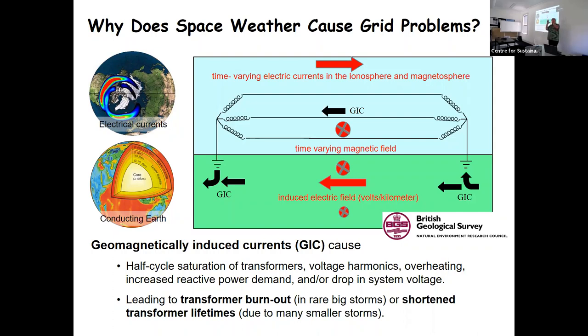It was the harmonics that ended up taking down Hydro-Quebec, but there was no actual damage to the equipment. It just pulled the whole network apart, but they could put it back together again. If, however, the saturation is bad enough, you start getting hotspots inside your transformer - hotspots are very bad - and at that point you can end up with burnout, and then you get actual equipment damage.